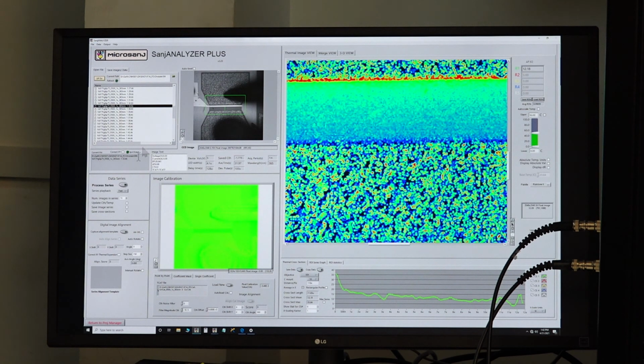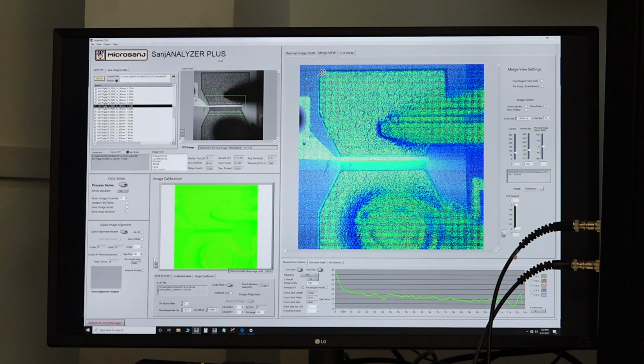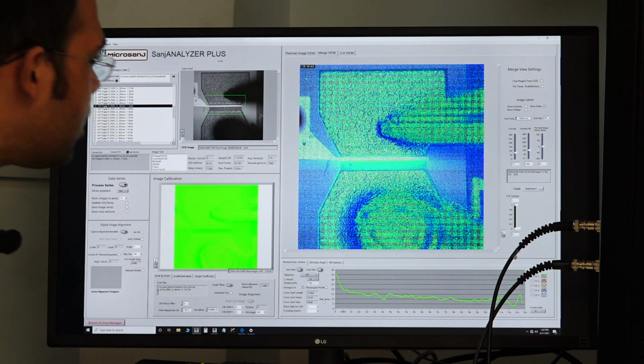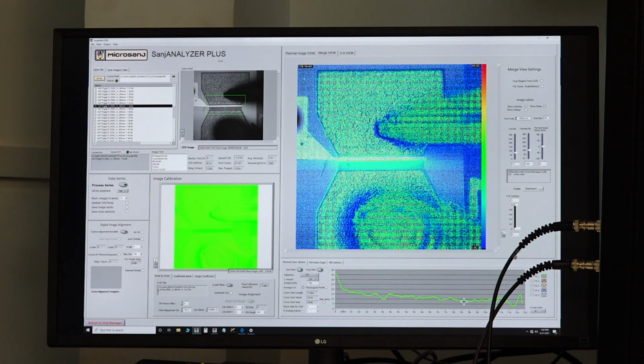In addition to this, we also have an option in which we can store this series as a video. For that, when you're presenting the data, you might want the users to have a feel of the delay, like the timestamp. So if you click on show delay, the timestamp comes in. If you want to show the color bar, that is the temperature scale, that comes in.